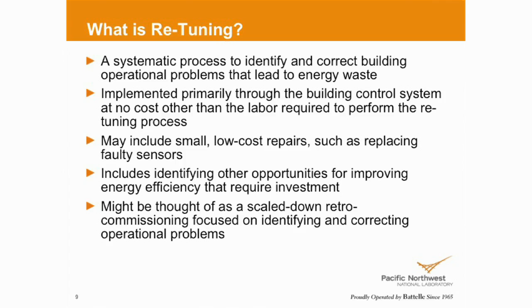So the bottom bullet there, we think of it as a scaled down retro commissioning effort. Retro commissioning, for those who've done those types of efforts, it's very detailed. It often involves a lot of paperwork, walking down all your HVAC systems, envelope, lighting, et cetera. If you want to go to that level of detail on a tuning effort, that's fine, but what we really emphasize with tuning or retuning is to focus it on the BAS.